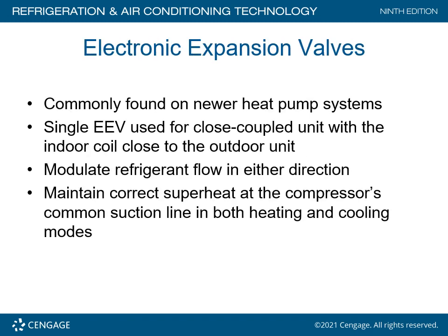Electronic expansion valves, you'll definitely see these a lot. Mini splits, a lot of them are designed, in fact most of them are designed as heat pumps. Commonly found on new heat pump systems, a single EEV, electronic expansion valve, is used for a close coupled unit with the indoor coil close to the outdoor unit. Modulates the refrigerant flow in either direction. Maintains the correct superheat at the compressor's common suction line in both heating and cooling modes.